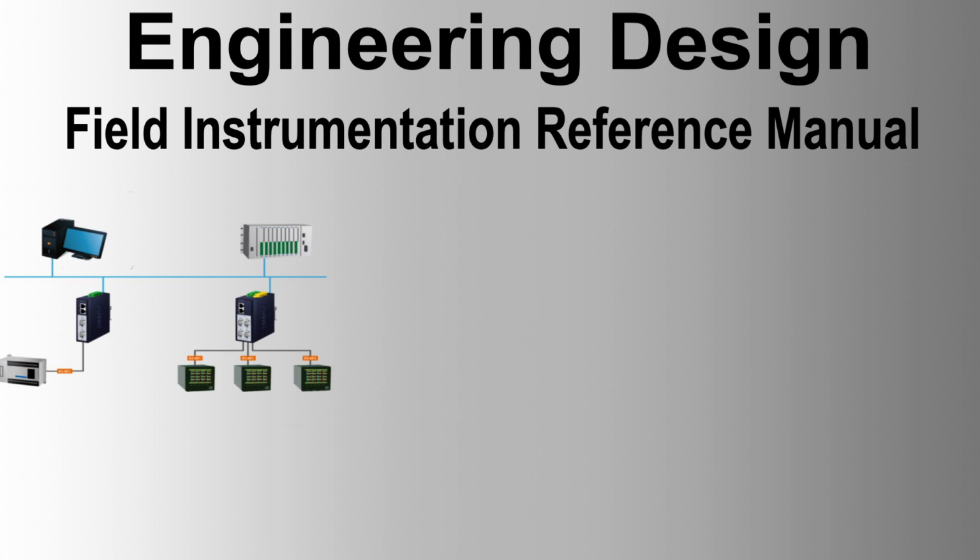4. Select adjusted range and accuracy. Ensure the selected range and accuracy meet the process requirements. 5. Select measurement options. Gather additional data required for the selected measurement principle. 6. Select suitable instrument types. Choose suitable makes and types from the approved vendors list, considering the types of instruments already installed at the principal's site to control variety.